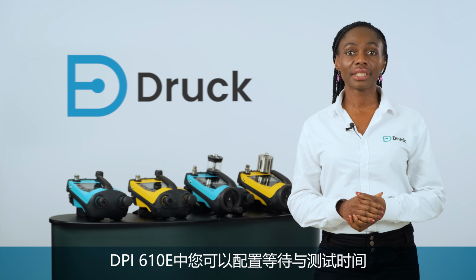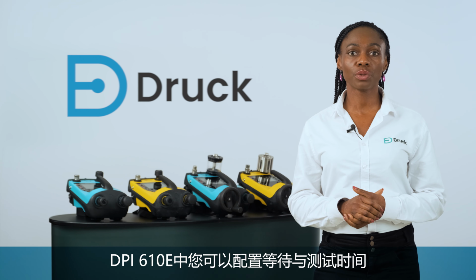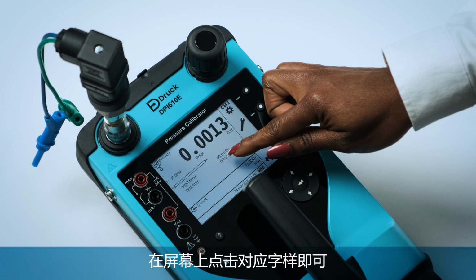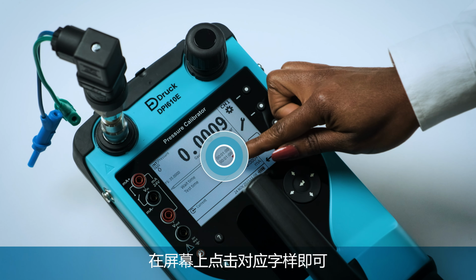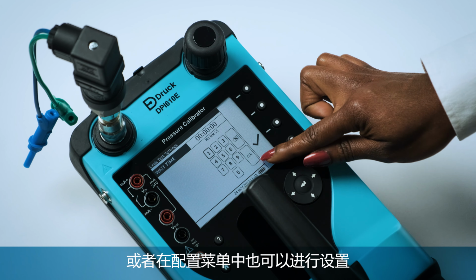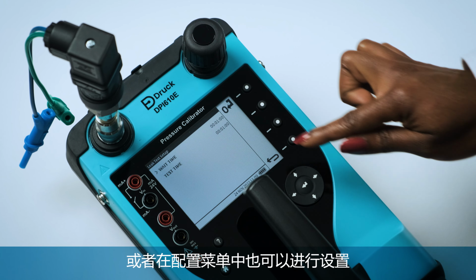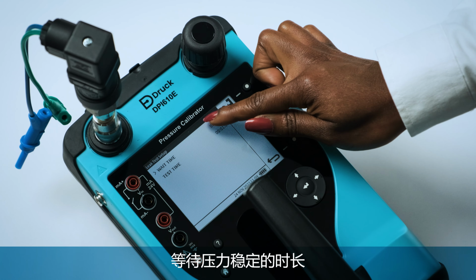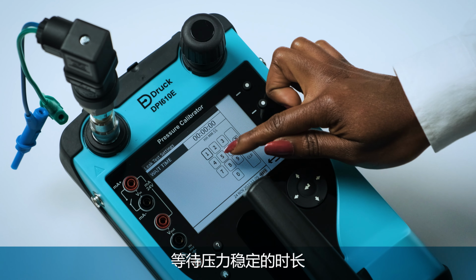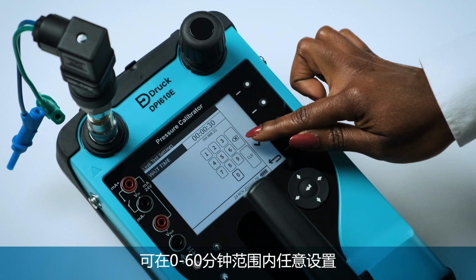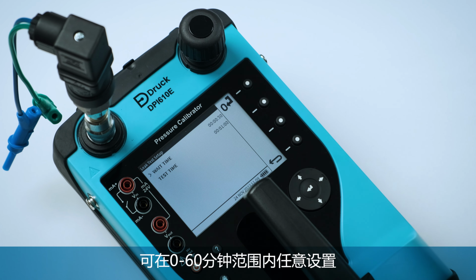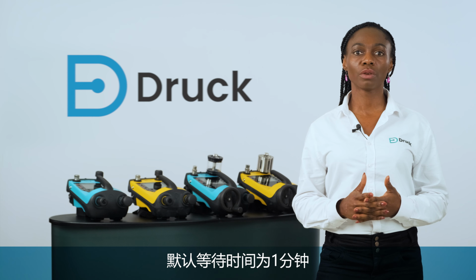The DPI610E allows the user to select suitable wait and test times from the main reading screen by tapping here or by accessing the leak test setup menu here. The wait time allows the pressure to settle before the actual test is started. This could be any value between 0 and 60 minutes. The default wait time is 1 minute.